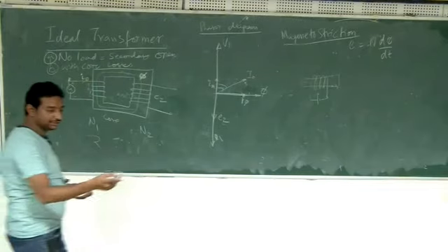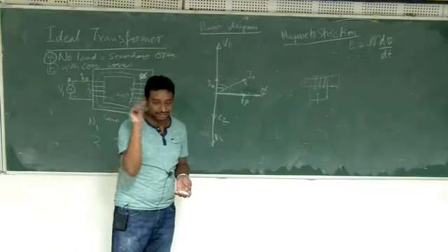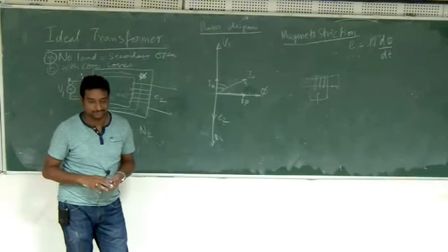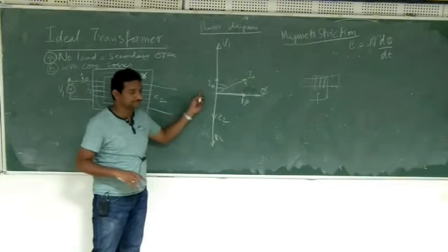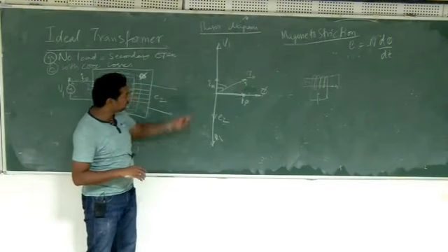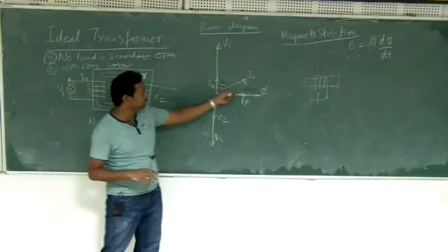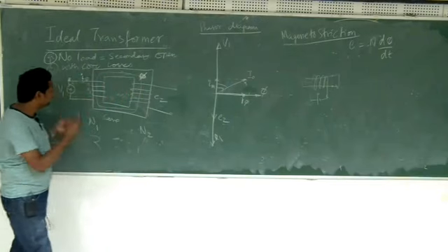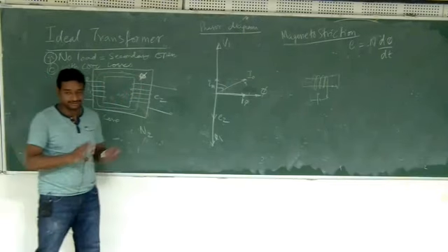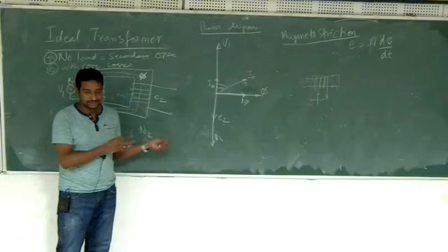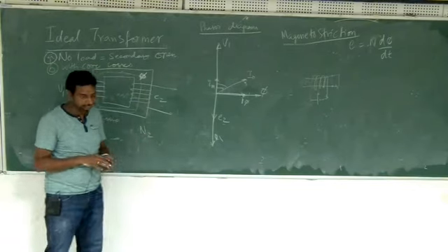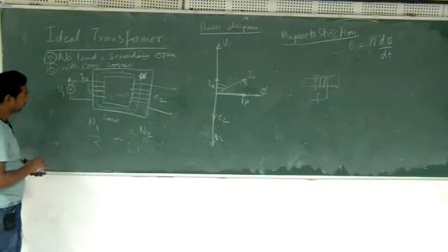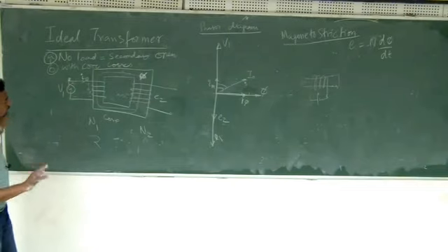So somebody mentioned we have to use resistance to represent the core loss. Okay. So how do you calculate that resistance? You know V and I. So simply divide V by I. You will get some value, but not this I. You will be measuring this I. So basically you do exactly the same thing. No load test on a transformer. Take a transformer, keep the secondary side open. In the primary side you do the no load test. Under no load conditions, how many watts it is consuming and all. We'll come to that. Now we'll discuss case C.